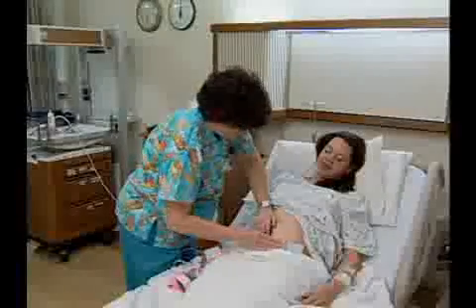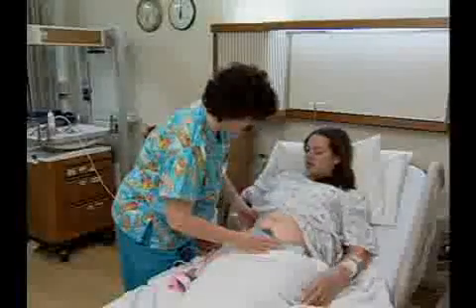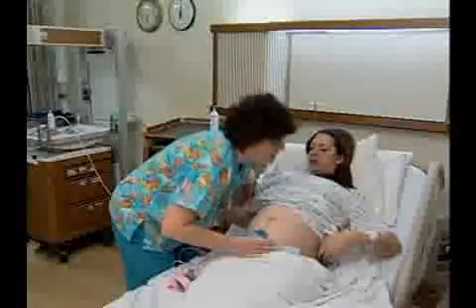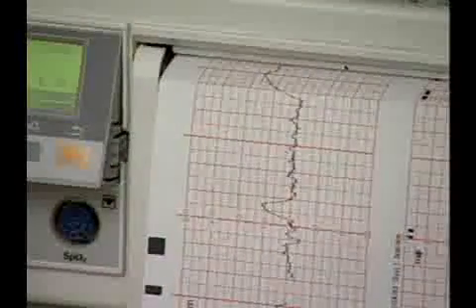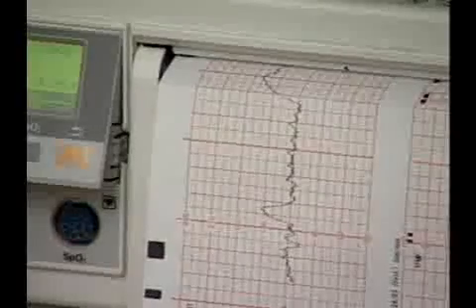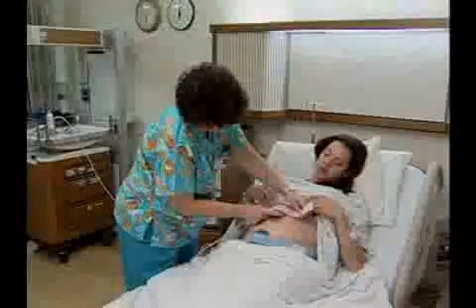With current technology, the recording from a well-placed ultrasonic transducer is very accurate. It picks up the movement of the valves in the baby's heart, which is transformed by the monitor into an audible output and a visual tracing.